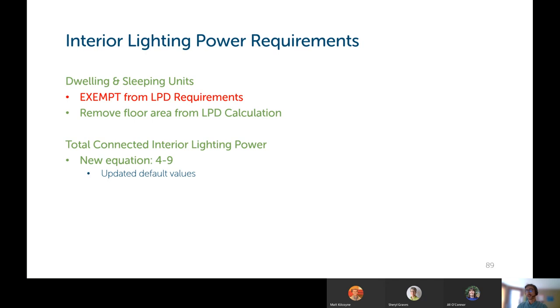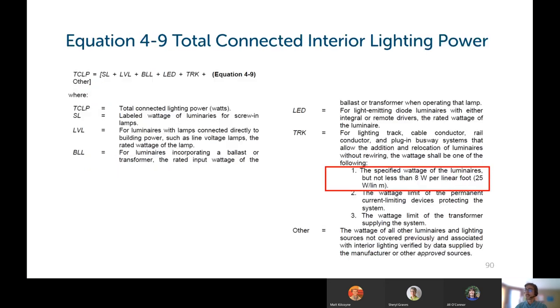Interior lighting power requirements. Dwelling and sleeping units are exempt from LPD requirements. They have their own high efficacy requirements. That's all you need to follow. You remove the floor area of all dwelling and sleeping units from your LPD, lighting power density, calculation. The total connected interior lighting power has been updated, equation 4.9. I'll go into that next. These are the different values that would be included in your lighting power density calculation. The total connected interior lighting power includes wattages from screw-in lamps, line voltage lamps, anything with ballasts included, LED lights, track lighting, and other luminaires. I will go into some more details on the next slide.